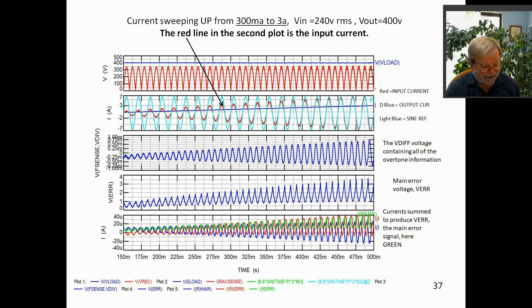The fourth plot is the composite error signal, combining the power factor correction and main loop error signals. The last plot shows the currents which make up the composite error signal. Red is the current from the output error loop, blue is the power factor correction signal, and green is the composite error signal, the sum of the other two.